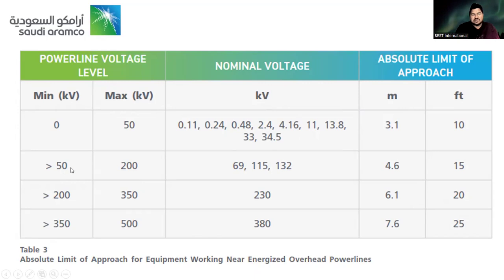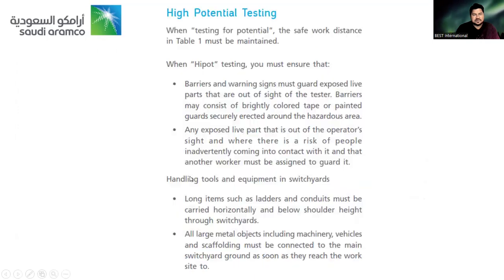Then as the voltage is increasing, the kVs are increasing, so you increase the distance also. The kVs are increasing, again you increase the distance. So for 350 to 500 kV, you go up to 25 feet and 7.6 meter. This is the absolute limit of approach for equipment working near energized power lines.